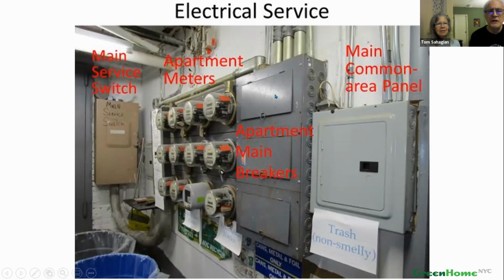The main breakers for all the apartments were two legs of 40 amps each. Initially there was a lot of arguing among the technical staff about whether that would be big enough, and whether we'd have to upgrade the service. After much discussion and some calculations, we concluded we did not need to upgrade the service, and that because the conductors from the apartment main breakers to the apartments were large enough, we could install 50 amp breakers instead. That gave us another 10 amps of headroom.